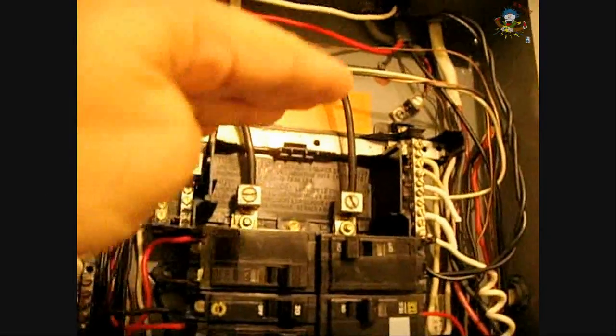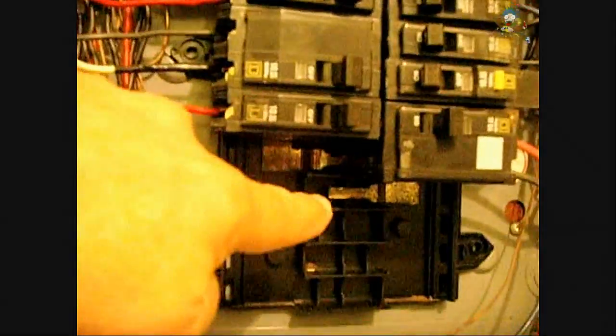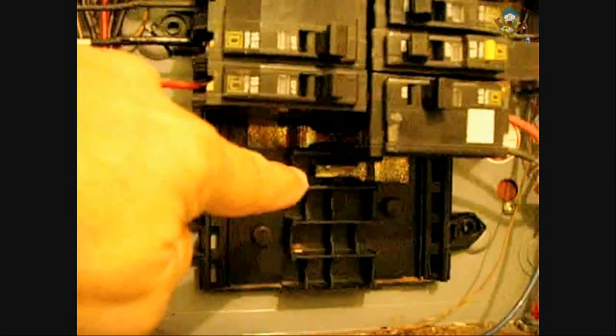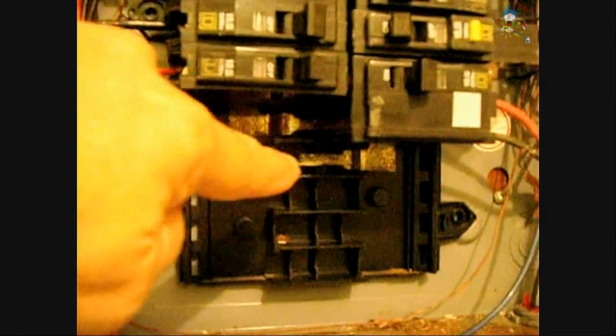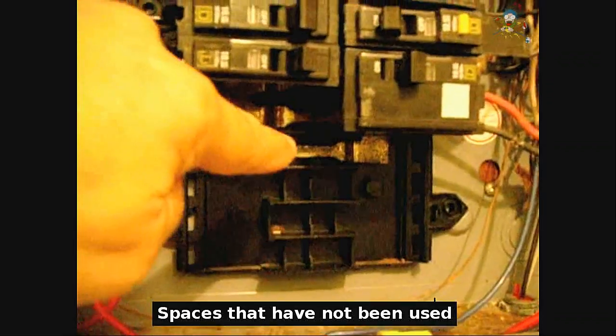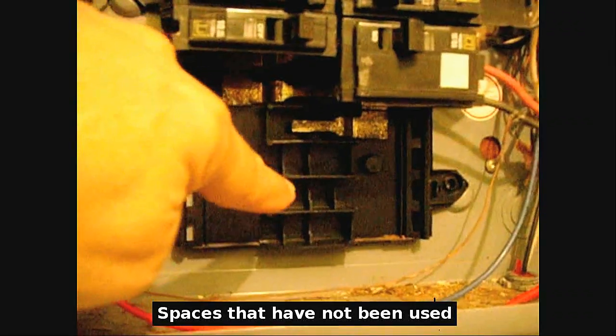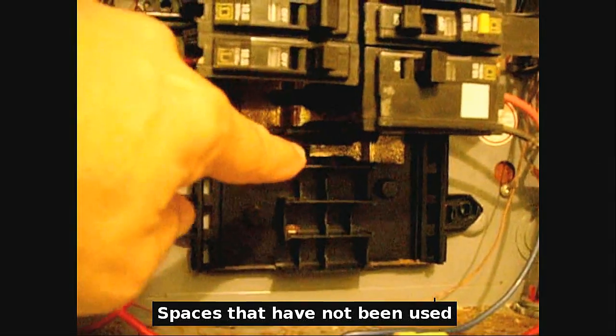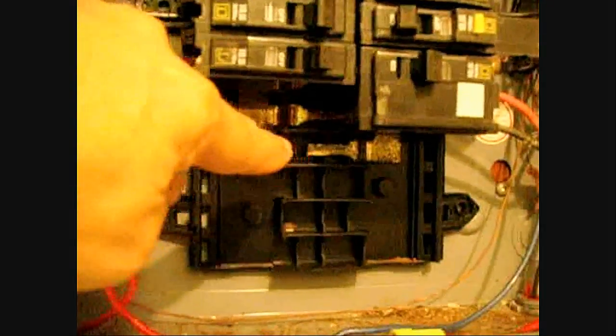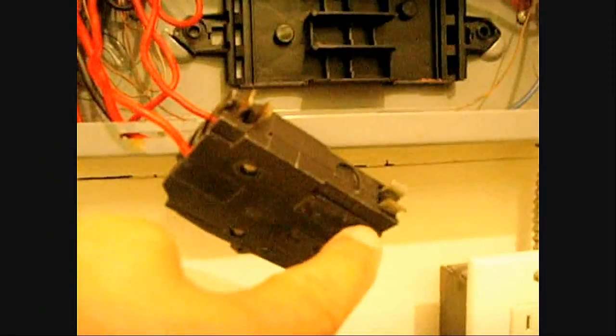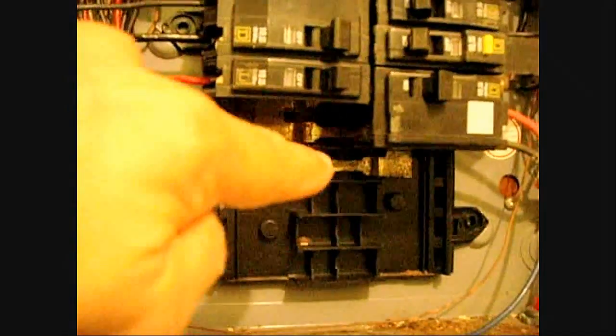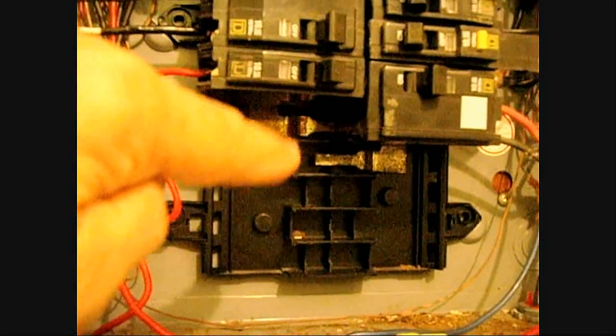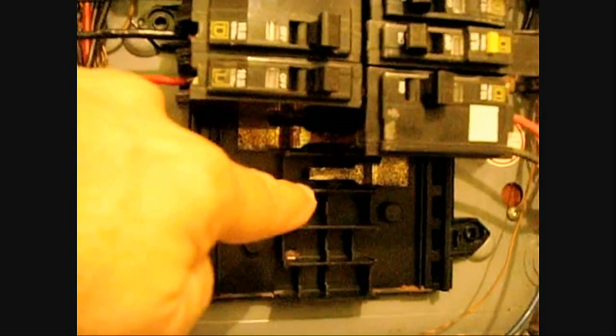If it is, make sure you shut the main breaker off to turn off all power to all the other branch circuits before you go anywhere near these connections to clean them. If you have a lot of spaces where the bus bars are perfect, then it would be a good idea to abandon where it's actually burned and pitted and move this breaker to a new location where it's not pitted. If you don't have a spot that's not pitted, then you're going to have to clean that very carefully.